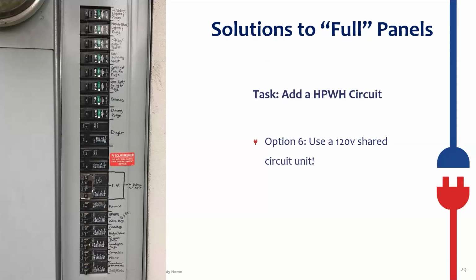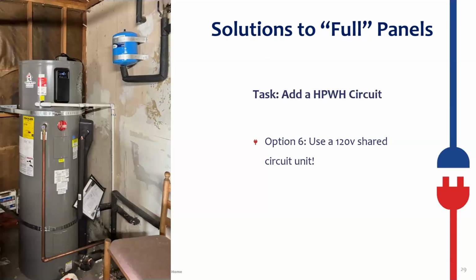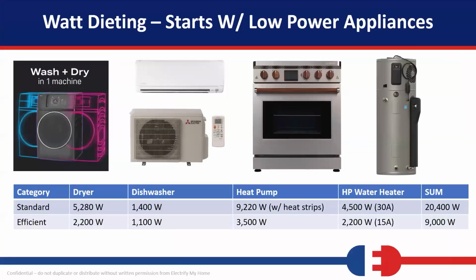Finally, instead of a 240-volt larger capacity heat pump water heater, add a shared circuit 120-volt unit. These units are now on the market - we need to be careful about when we add them, but they do exist now. On that same theme, we call it watt dieting: start with low power appliances. This is always a great first solution. All the ones shown at the top here are 120-volt options to decrease the load to begin with, so we can squeeze more into lower capacity.